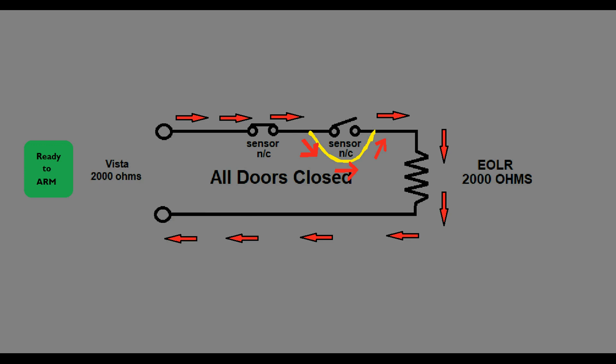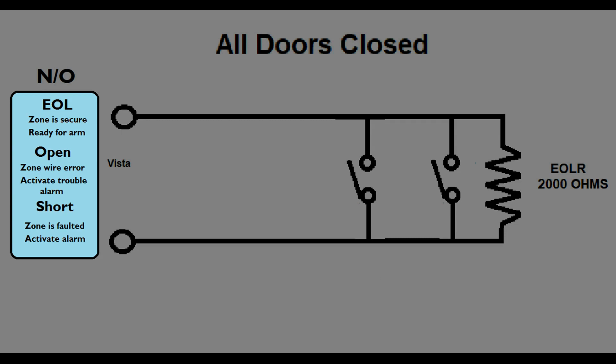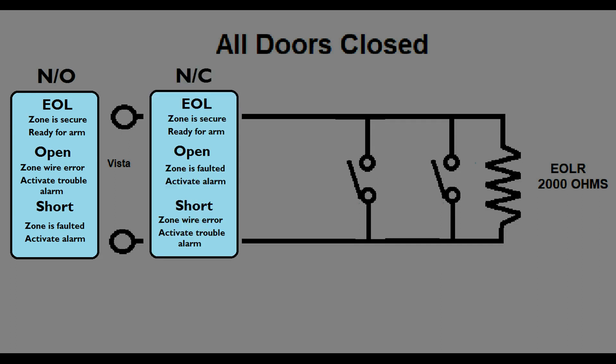Let's look at sensors hooked up in the normally open configuration. Just like before, the Vista will be looking for one of three possible conditions on your circuit: end of line resistor, open, or short. No matter which sensor you're using, the end of line resistor has the same effect on the Vista.